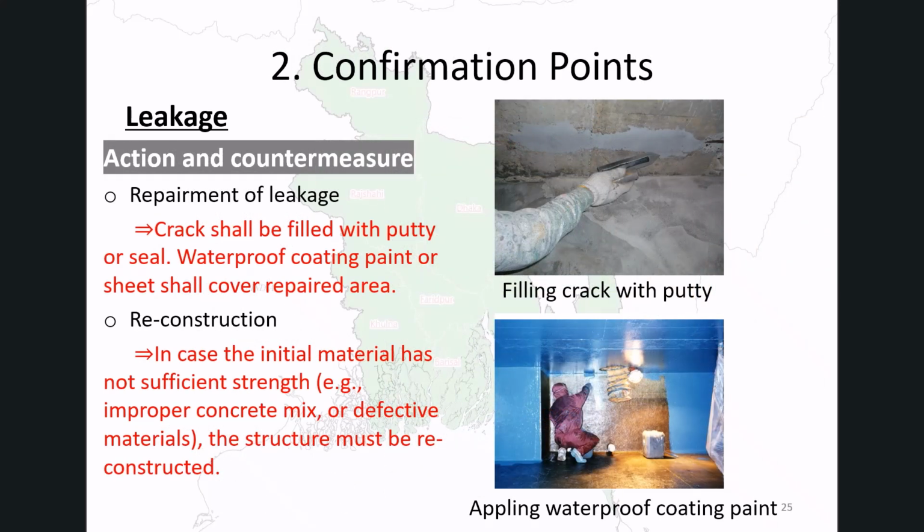As a countermeasure against leakage, repairs can be carried out. Cracks in concrete are filled using putty or sealing materials, followed by the application of waterproof coating. If deterioration is caused by insufficient strength of the original tank materials, it may be necessary to reconstruct the facility itself.